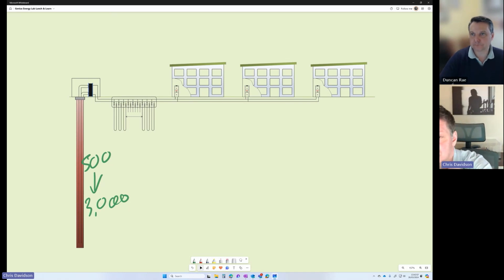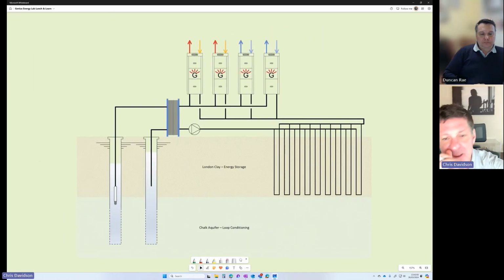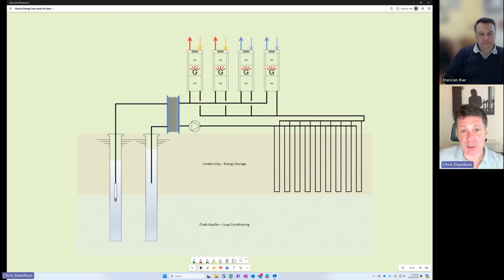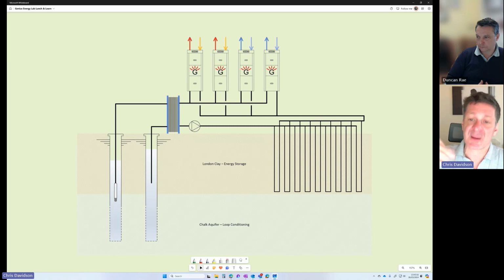So just a mention of that. Finally, bringing everything we've talked about together in a hybrid system - this has been up and running for over 15 years now, a building called One New Change. If you imagine standing on the dome of St Paul's Cathedral looking east, it's at your feet there. It's 3 or 4 layers of shops and restaurants, then 3 or 4 layers of offices with a lovely rooftop restaurant at the top - highly recommended, particularly in the summer, a great place to be. The brief on this building from Landsec, the building owner, was to do as much as we possibly could with the geology available to us.